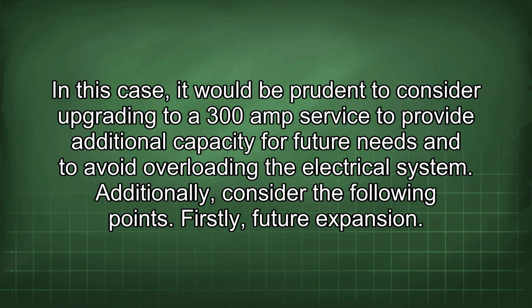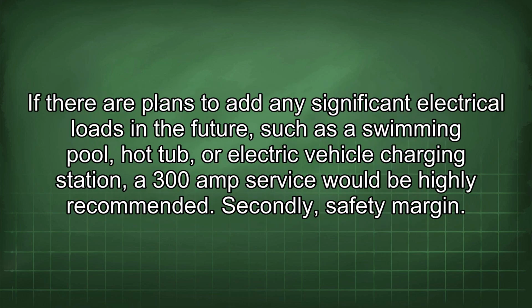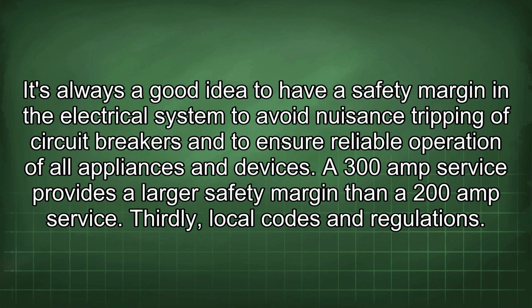In this case, it would be prudent to consider upgrading to a 300 amp service to provide additional capacity for future needs and to avoid overloading the electrical system. Additionally, consider the following points. Firstly, future expansion. If there are plans to add any significant electrical loads in the future, such as a swimming pool, hot tub, or electric vehicle charging station, a 300 amp service would be highly recommended. Secondly, safety margin. It's always a good idea to have a safety margin in the electrical system to avoid nuisance tripping of circuit breakers and to ensure reliable operation of all appliances and devices. A 300 amp service provides a larger safety margin than a 200 amp service.